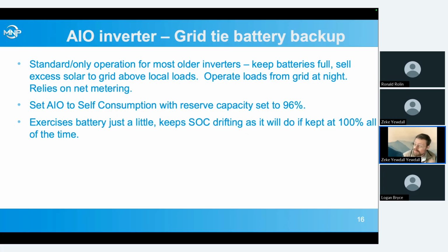That would work for a while and it would just keep the batteries completely full, never pulling power off of them. But it can have the state of charge drift from reality due to not seeing those low currents each night. So by setting it down a little bit, it prompts it to actually top it off each day and keeps it better in sync.